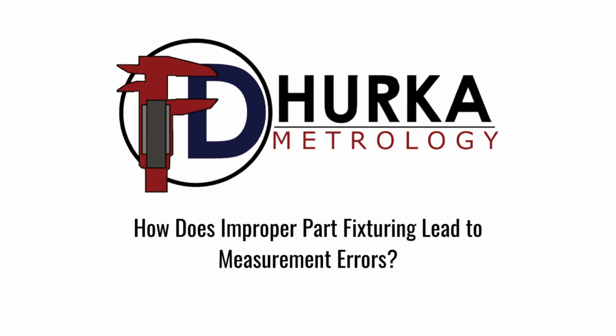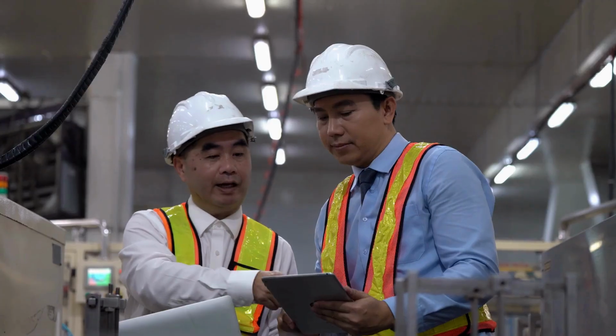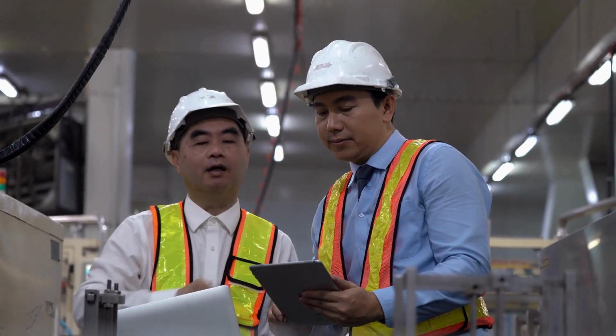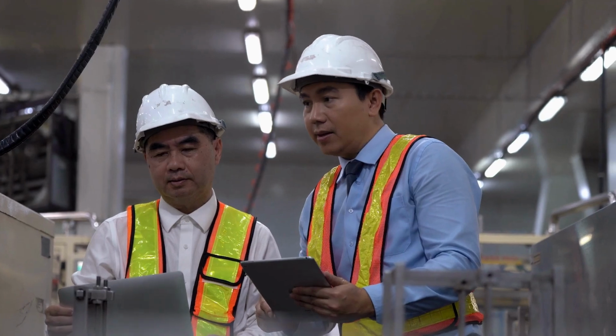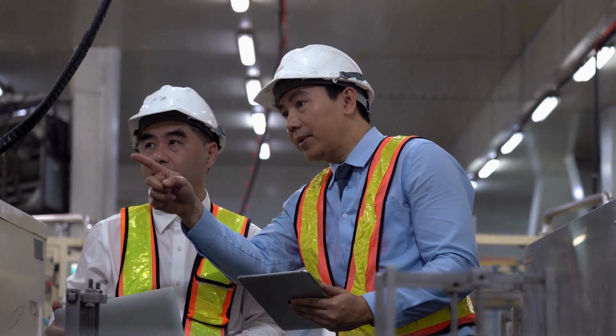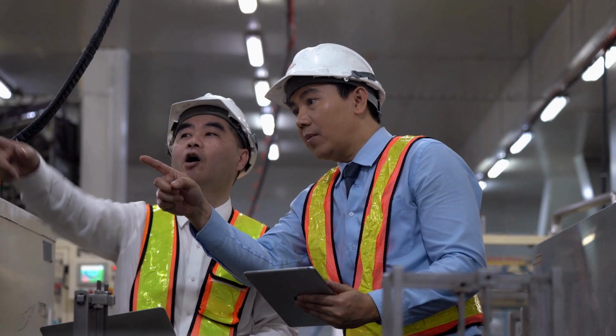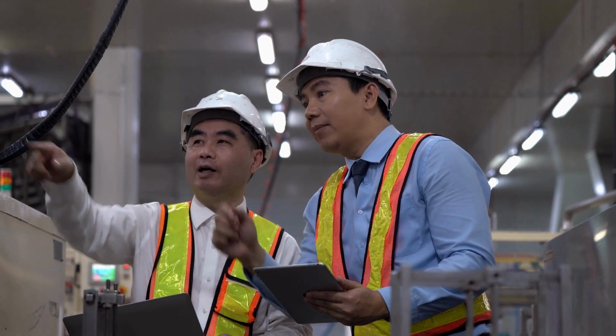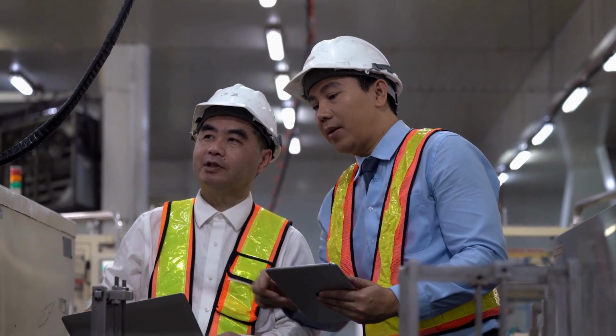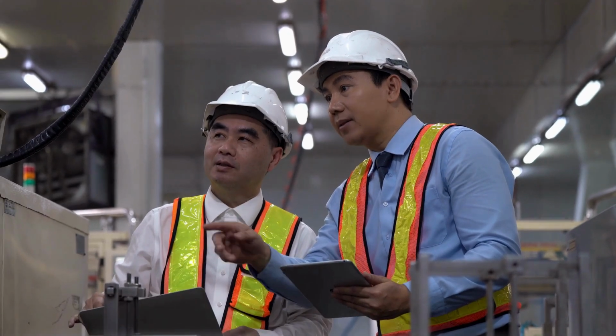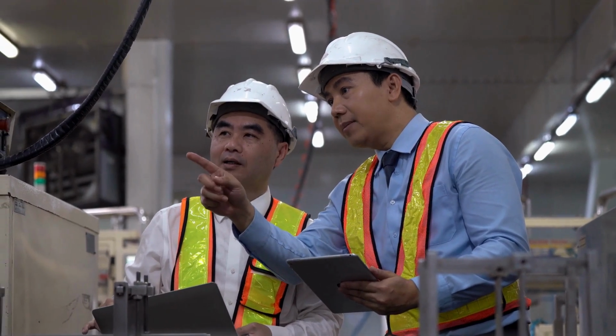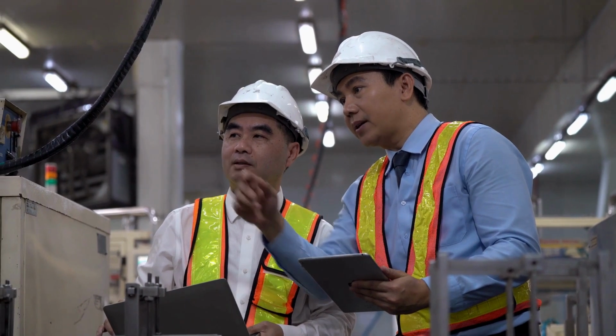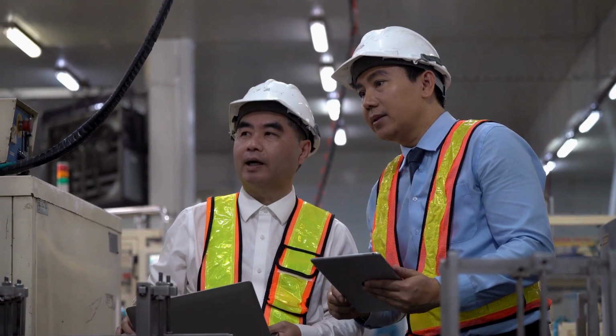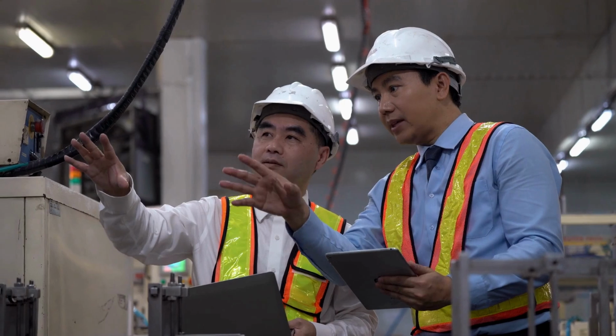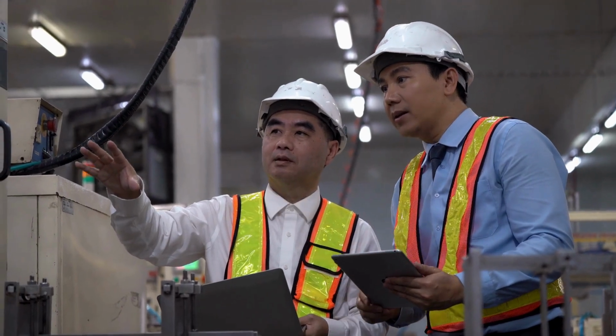How does improper part fixturing lead to measurement errors? Parts that are not secured properly can move during measurement, and even a slight shift when the stage moves produces blurry or misregistered images that lead to incorrect dimensional data, which is a mistake that looks like a system error but is actually a part handling problem that is fully preventable with the right fixture plates, clamps, or vacuum holders appropriate to the part geometry.